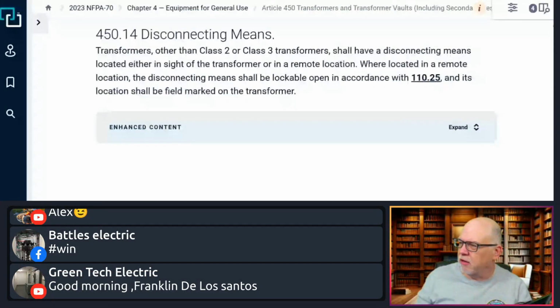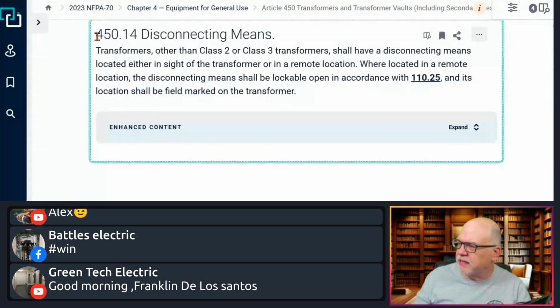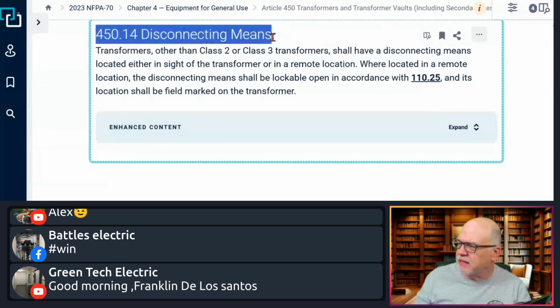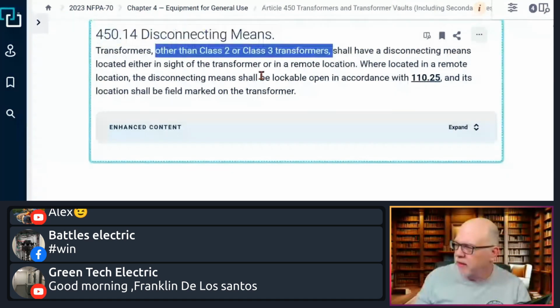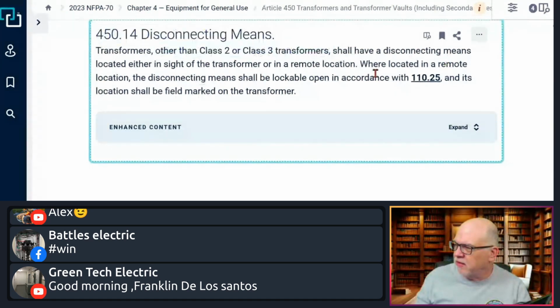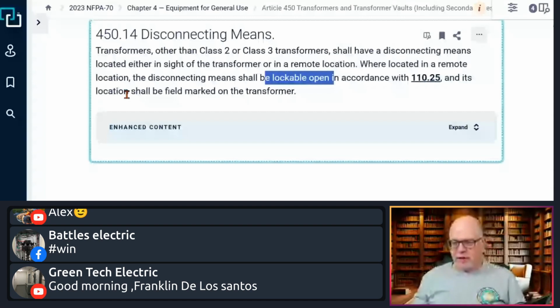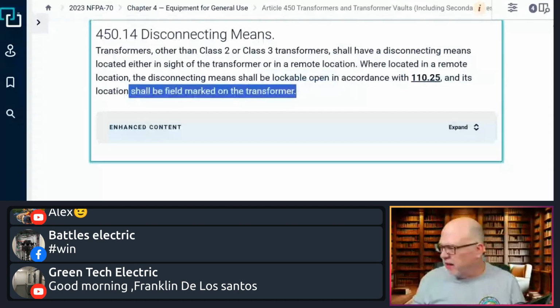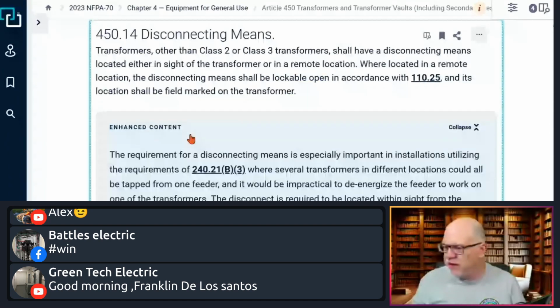We're right here. So here is 450.14. There's the disconnecting means. And again, other than class 2 or class 3 transformers, it says shall have a disconnecting means located either in sight of the transformer or in a remote location. Where located in a remote location, The disconnecting means shall be lockable open in accordance with 110.25, and its location shall be field marked on the transformer. So that's the rules, and there's really no additional commentary here.